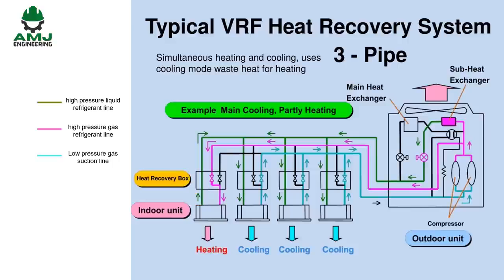The heat recovery unit combines high-pressure liquid exiting heating zones with high-pressure liquid from the outdoor condensing unit and directs it to any indoor terminal units that are in cooling. The cooling mode indoor terminal unit acts like an evaporator, and the refrigerant exits as low-pressure gas, returns to the heat recovery unit, and then proceeds to the outdoor condensing unit to begin the cycle again.